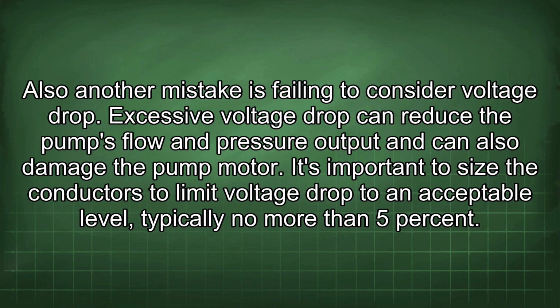Also, another mistake is failing to consider voltage drop. Excessive voltage drop can reduce the pump's flow and pressure output and can also damage the pump motor. It's important to size the conductors to limit voltage drop to an acceptable level, typically no more than 5%.